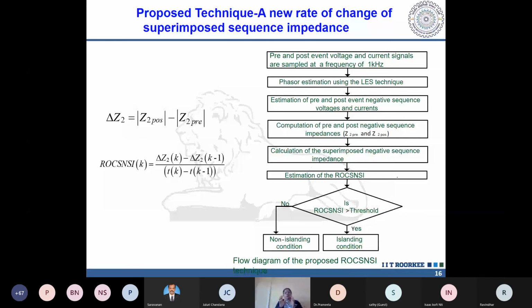Superimposed means the difference between the present situation and the previous situation. You subtract them, and that difference is the superimposed sequence impedance, delta Z2, equal to Z2 post minus Z2 pre. We calculated this component and set some threshold. In our technique, the major drawback is the threshold setting, but the major advantage is that we have overcome the NDZ problem.